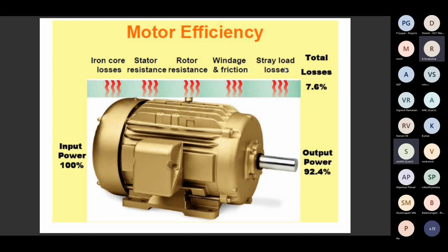So approximately, this particular motor data is shown as an IE3 motor. IE stands for international efficiency. Now the Bureau of Energy Efficiency and the government also recommend that industry install energy efficient motors. Now don't go for inefficient motors. If you give 100% input power, the effective output is 92.4%. The remaining 7.6% goes to various losses, even for an IE3 motor.